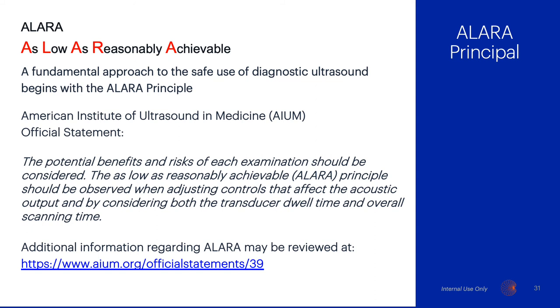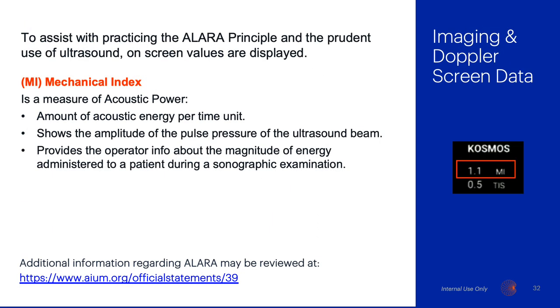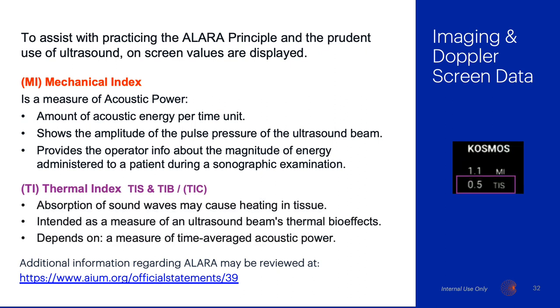The American Institute of Ultrasound in Medicine has numerous publications that may be reviewed for further information. To assist in practicing the ALARA principle, on-screen values are displayed to include the MI, or Mechanical Index, and TI, or Thermal Index. The Mechanical Index is a measure of acoustic power and provides the operator information about the magnitude of energy administered to a patient during a sonographic examination. The TI, or Thermal Index, relates to the absorption of sound waves that may cause heating in tissue and is intended as a measure of an ultrasound beam's thermal bio-effects. A working knowledge of MI and TI is encouraged, and additional details may be reviewed in the various AIUM publications.